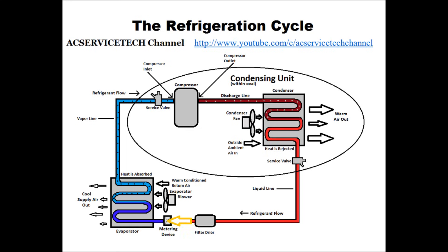After the filter dryer it hits the metering device. The metering device allows for a pressure change. You have high temperature, high pressure liquid refrigerant coming into the metering device, and it turns into a low pressure refrigerant — which automatically makes it a low temperature as well. If you decrease pressure, then temperature will decrease. The metering device is only going to allow a small amount through, and it turns into a low pressure, low temperature, 80% liquid, 20% flash gas mix — mainly a low temperature, low pressure liquid.